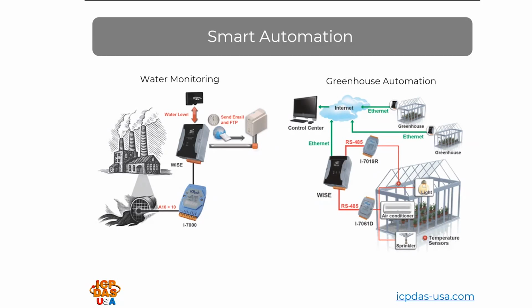The I7000 series data acquisition modules are used to log measurement levels of hazardous chemicals and wastewater runoff from manufacturing facilities. The data is logged on a micro SD card in the WISE 5800, then an email gets sent out based on a schedule with the data log. The data log is also retrievable over FTP. When the level of chemicals starts to get close to an unsafe level, email alerts get sent out, so the manufacturing at the plant will stop and maintenance will be performed to prevent hazardous conditions.